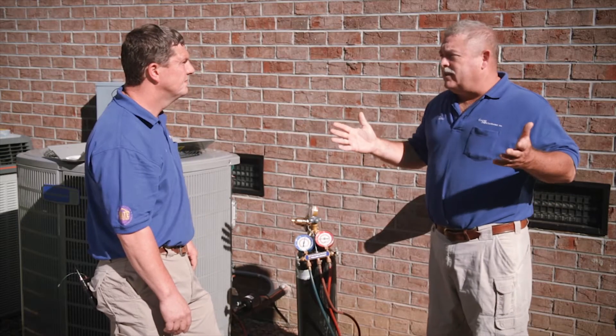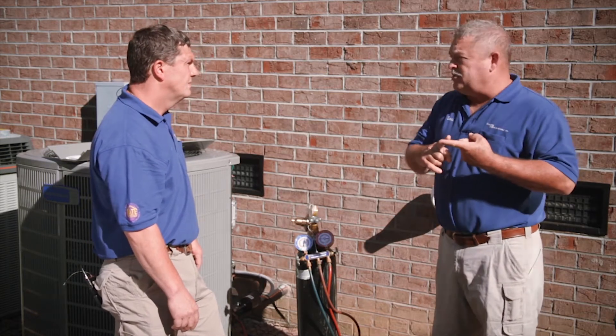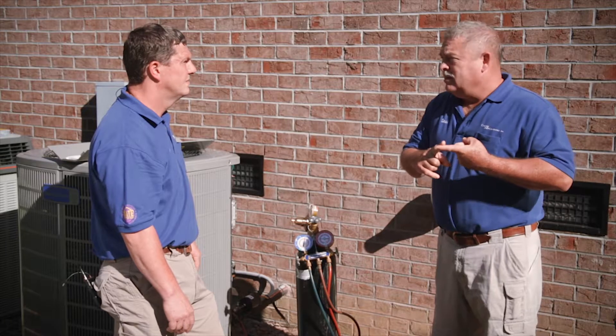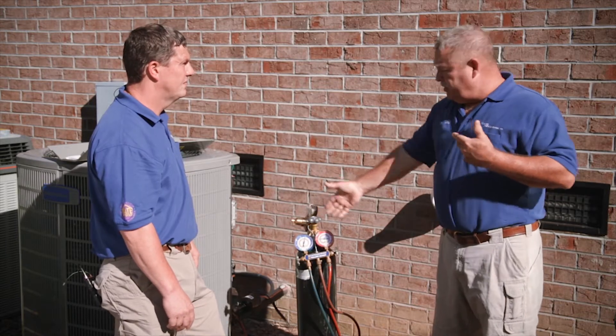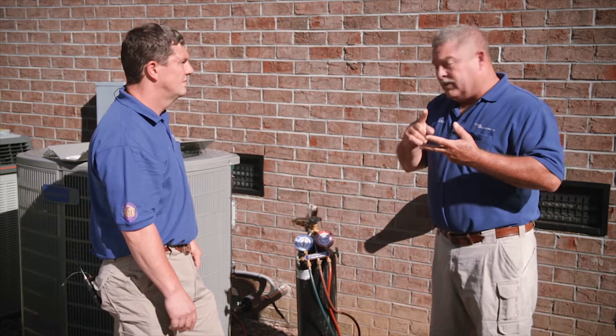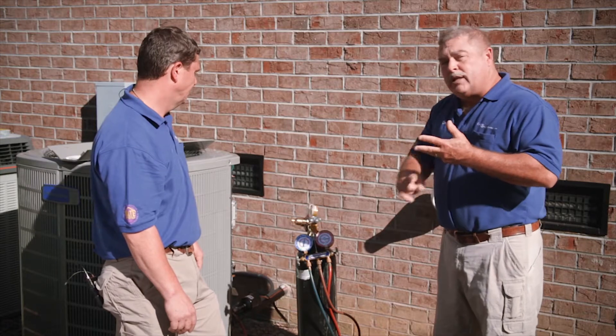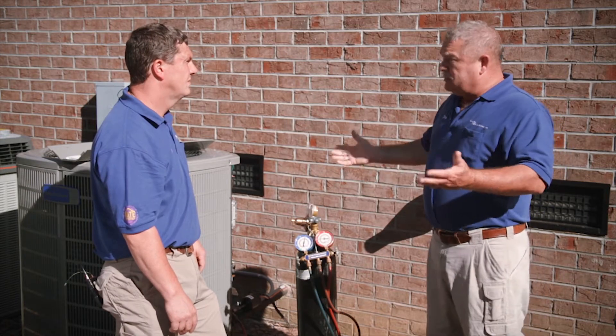We basically protected ourselves and the homeowner. Number one, we've ensured our sweat joints that we soldered aren't leaking — that's the insurance, we know the system's right. Number two, we know that we've cleaned the system properly, that it's been sorted and the charge is going to be right. And number three, we're getting any extra moisture out of it. That's correct.